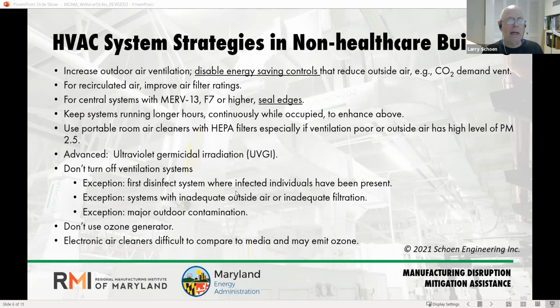Please stay away from anything that is either listed as an ozone generator or that hasn't been certified to not release ozone. And I know there's a lot of heavy marketing of electronic air cleaners and introducing hydrogen peroxide and anything that says ions or plasma. There's a lot of marketing of that. I can't say definitively they don't work. It's hard to prove a negative, but they do need to be proven that they actually do some good. I would not substitute those for good filtration by mechanical means and good introduction of outdoor air.